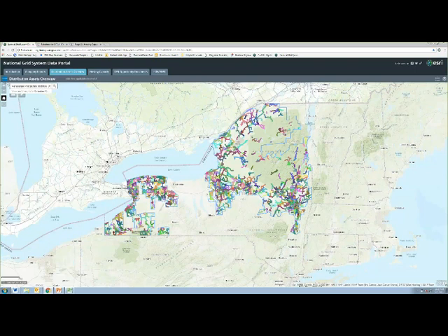So we have a roadmap set of different stages to meet. Stage 2 was the feeder level information that we completed, but we added on stage 2.1, which was that substation level information, so things like the DG installed and connected, the historical peak. So that was to bridge the gap between stage 2 and stage 3. And stage 3, we will show nodal level hosting capacity numbers. So you click on a feeder and you can say from section A to section B, you have a certain hosting capacity number, and so on throughout the feeder.